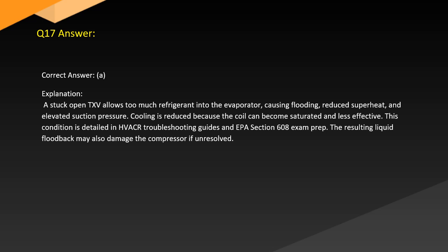Answer. Correct answer: A. Explanation. A stuck-open TXV allows too much refrigerant into the evaporator, causing flooding, reduced superheat, and elevated suction pressure. Cooling is reduced because the coil can become saturated and less effective. This condition is detailed in HVACR troubleshooting guides and EPA Section 608 exam prep. The resulting liquid floodback may also damage the compressor if unresolved.